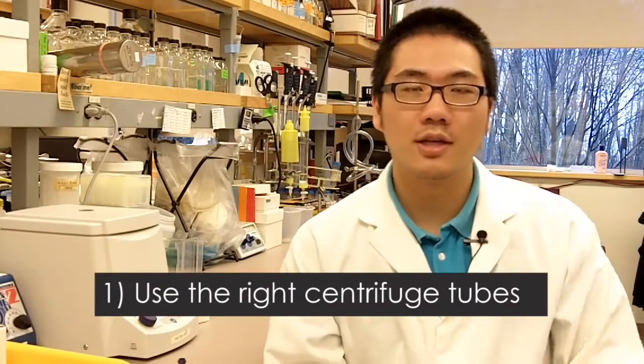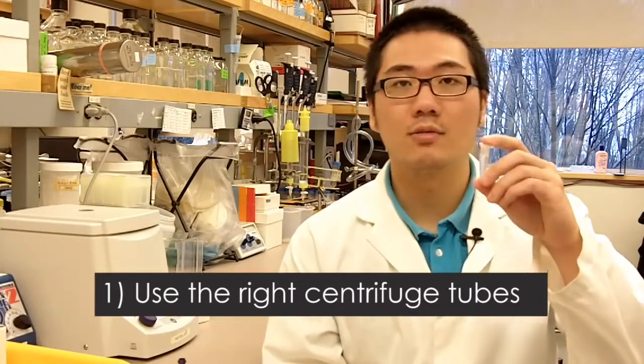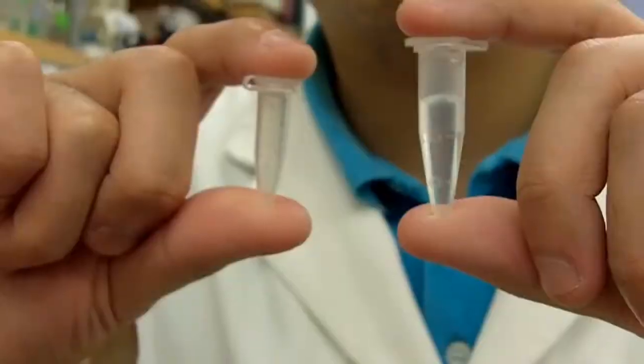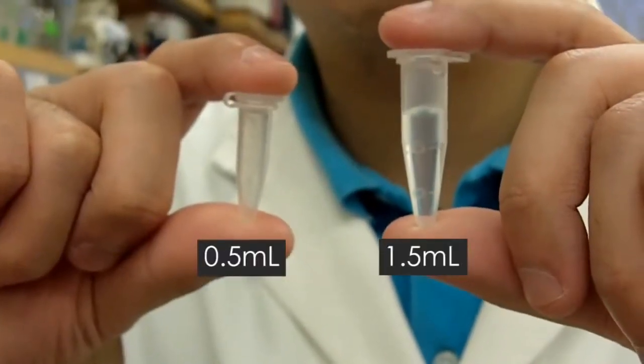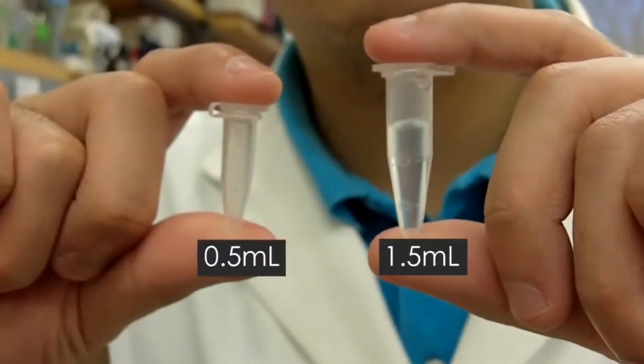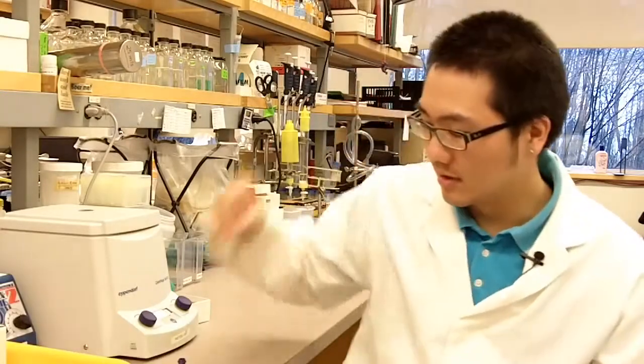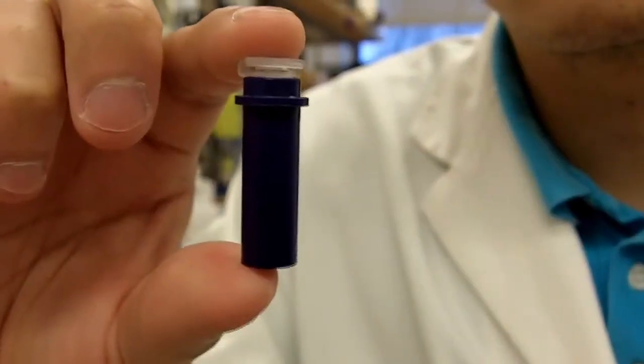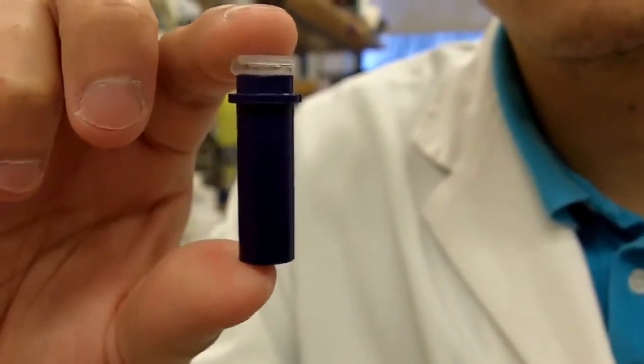The first thing you need to know when you use a centrifuge is to make sure you use the right size of tube for the right centrifuge. Here is a commonly used 1.5 mil microfuge tube that fits in most of the tabletop centrifuges. Here is a 0.5 mil microfuge tube that would also fit into the centrifuge. But if you use this one, you'll have to use an adapter. So you place it in an adapter like that and use it. If you don't, the tube might break.